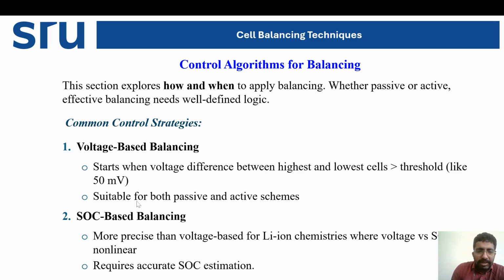It is suitable for both passive and active schemes. Until the threshold is crossed, there won't be any initiation of balancing; the cells will charge as usual. Once the threshold is crossed, as per the algorithm, something needs to be transferred using active schemes, or something needs to be dissipated using passive schemes.